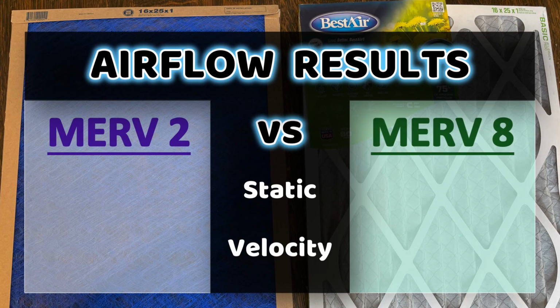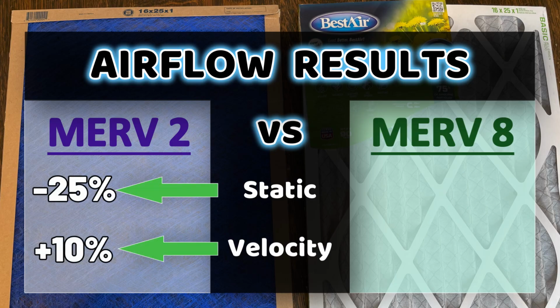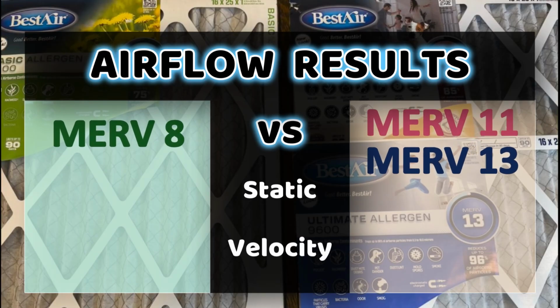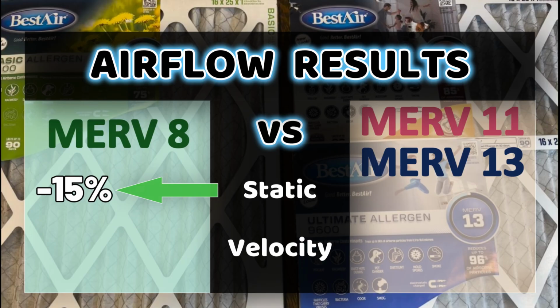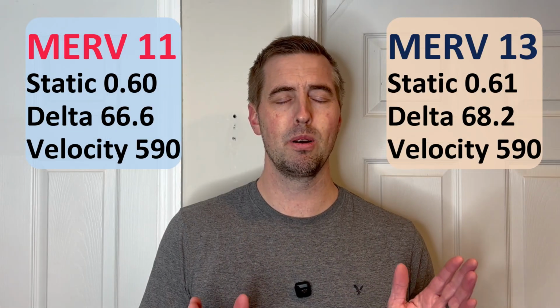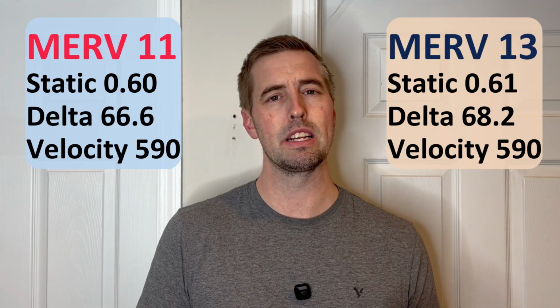And looking at the results, MERV 2 resulted in 25% less static and about 10% more airflow than the MERV 8. While this may not seem all that significant, we're going to see just how big of an impact it had on our temperature delta here shortly. Now if we pit the MERV 8 against the MERV 11 and 13, we see that the MERV 8 had 15% less static and 5% more airflow than the two higher rated filters. And speaking of which, the MERV 11 and 13, that was a bit of a surprise. Both filters had pretty much identical static and airflow readings, and I'm assuming this may be due to differences in the pleat design or filter material, and I plan to have a separate video that's going to dive into this further.